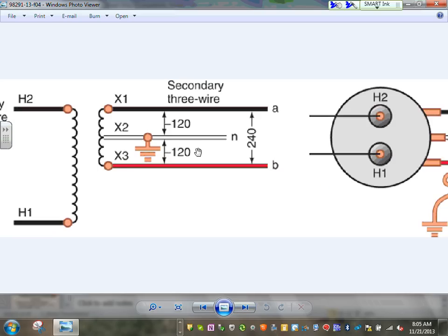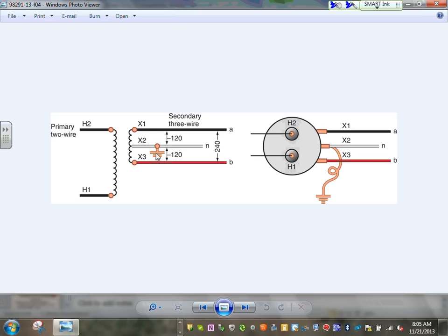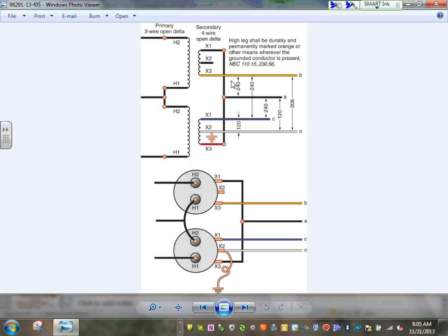Connection of transformers that we talked about. Here's how they connect the transformer. Single phase. That's how you get your single phase transformer. Look at the high voltage, low voltage. You can also have 240/120 open delta. Open delta 240/120 center tap, they call it. Can you guys see how the connection is? Again, the expectation is not that you're going to be an electrician, but if somebody asks how you wire an open delta, I would hope that that's how you connect them. You guys have done that. You should have done that in the second semester with us.